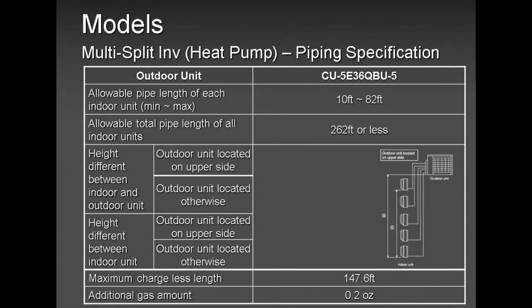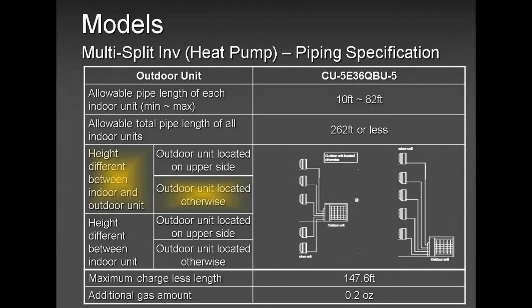This is what I was just talking to you about. This is what it's explaining here. This slide is just to make you aware that there are clearances and there are pipe distances in place that you need to be aware of. Don't just install an indoor unit for the sake of installation or because the homeowner asks you to, and you're breaking these rules. You're breaking the height differences between outdoor, indoor, indoor, outdoor, outdoor below, indoor below, and all that stuff.